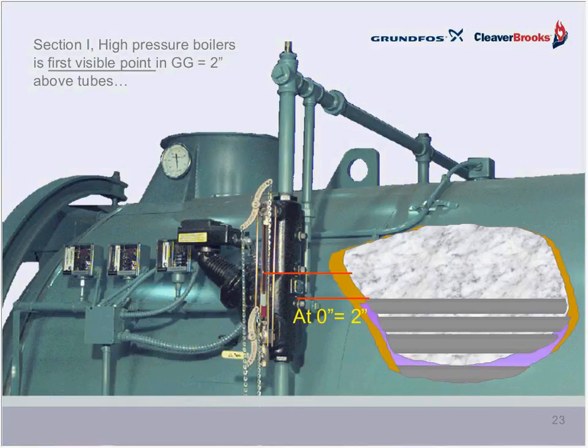Oh, and by the way, before going any further, I also wanted to mention that regardless of what low water cutoff and pump control option one chooses, of which there are many choices, it has to be mounted specifically and accurately so as to reflect the actual level of water in the boiler's shell or drum. Now, here you see it mounted on a fire tube boiler with specific mounting dimensions for ASME Section 1 of the code, and that would be, of course, in the case of high-pressure steam boilers, Section 1. Note, we want 2 inches above the top layer of tubes at the first visible point in the gauge glass. Very important, as we certainly don't want anything to happen, as I showed you just a minute or two ago.